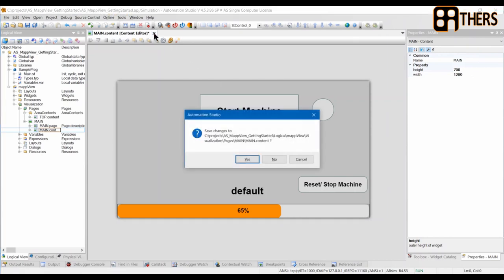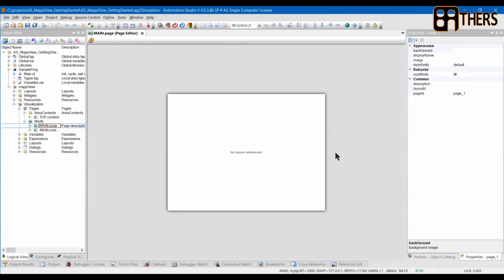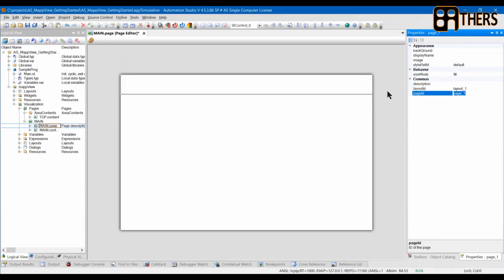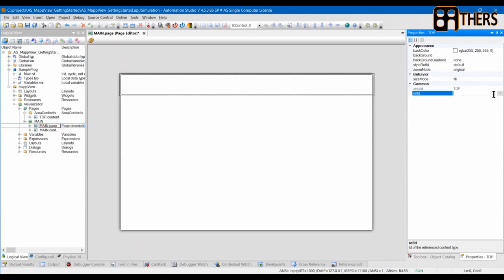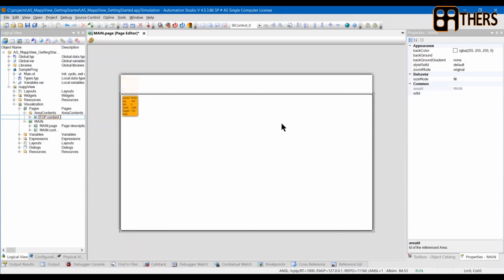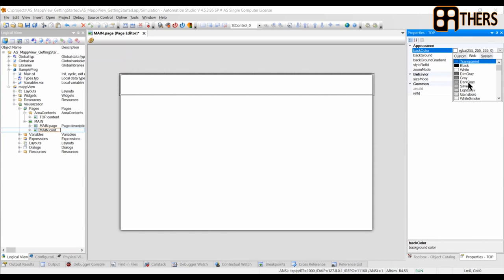Our design should be done. Now go to the main page and set the Layout ID to our layout name 'Layout1'. The Page ID we'll call 'main' — this is very important as you have to copy the name to the binding in the .vis file later. Then click on the top area and select the reference ID of 'top' as defined. Select the content area and assign it to 'main' as defined. You can also set the background color — for example, dark grey and dim grey.